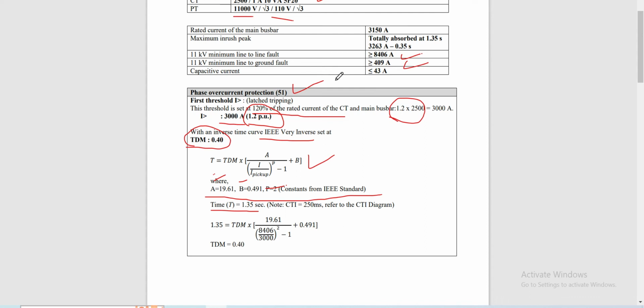Our fault current at 11 kV minimum line to line is 8,406. That's why we have this information. And our pickup current is 3,000 amperes. We also substitute the IEEE standard constants from here. After we calculated the result, the time dial multiplier is 0.40, and we reflected this information from here. This is for the first threshold of our phase overcurrent protection.